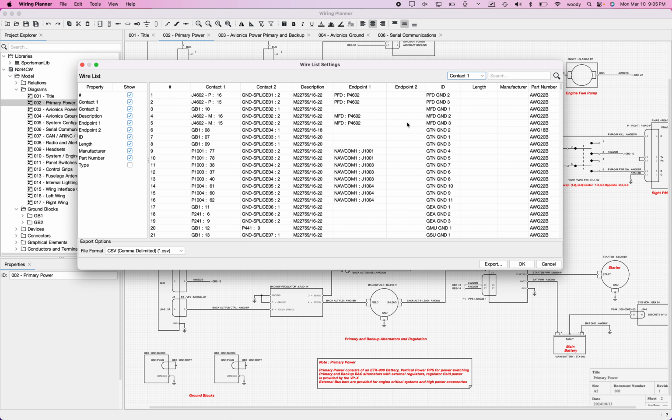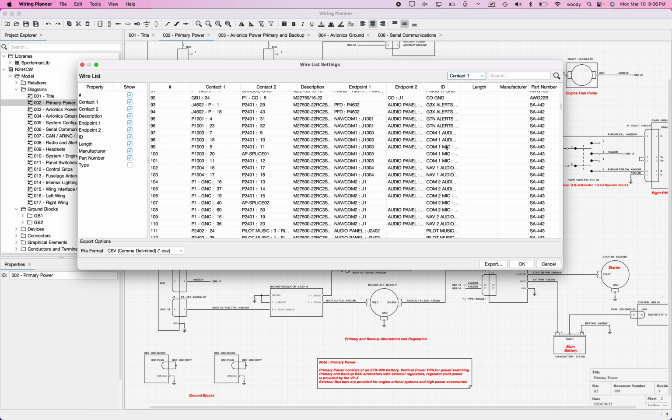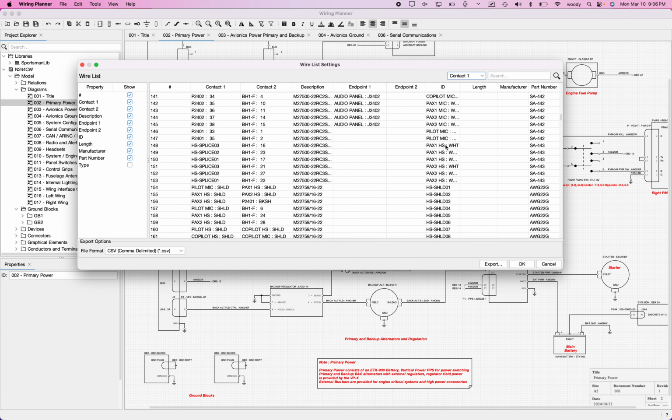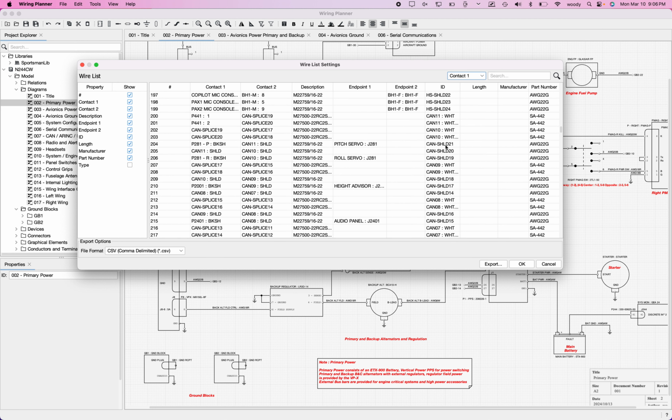Obviously, the two things we would predominantly have here are single conductors and multi-conductor cables. In my case, I will show you a cable in my CAN bus, which is right here. You'll see the way we identify that, even though you wouldn't name the cable, you would name your conductor. And when the cable is designed in the library, it's got a white conductor and a white and blue conductor. And that's the way a cable is designated. So you can see they go together.